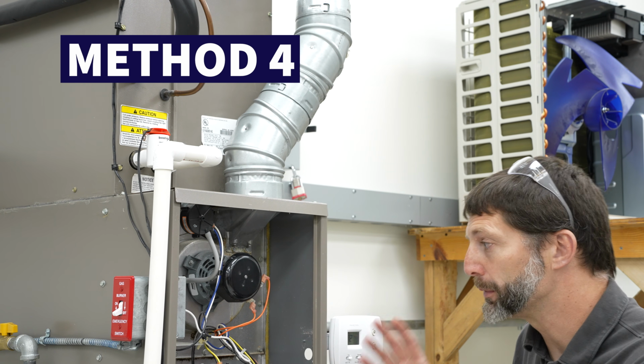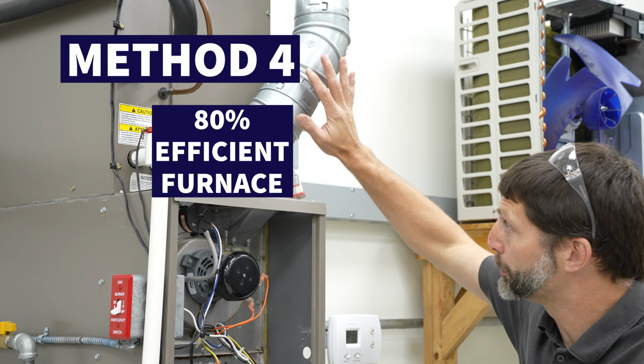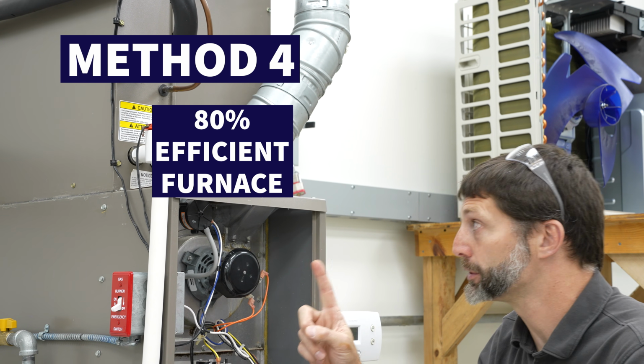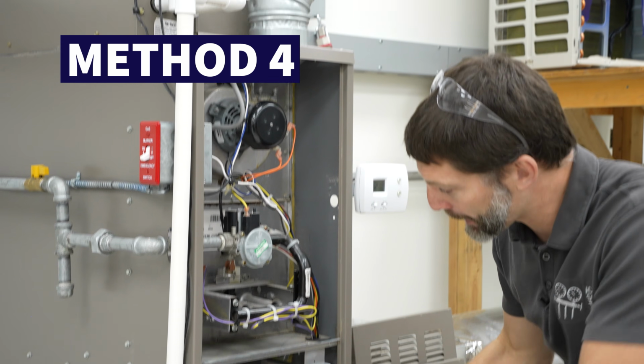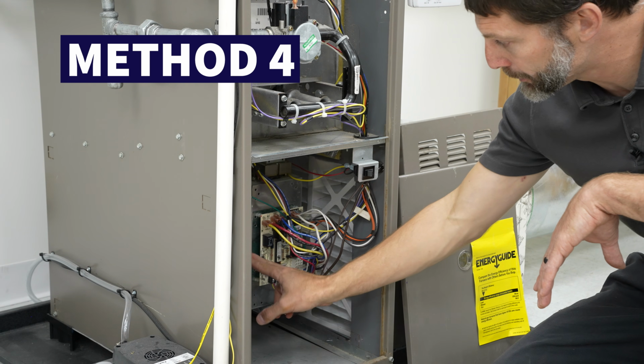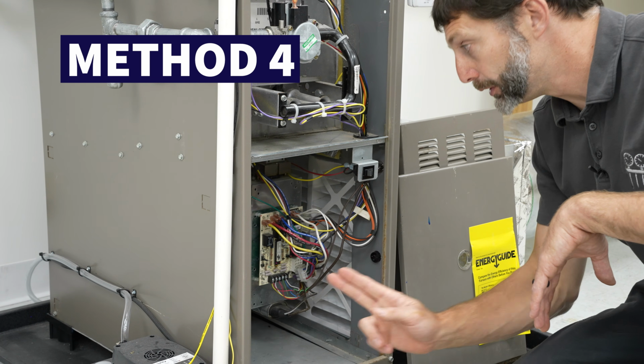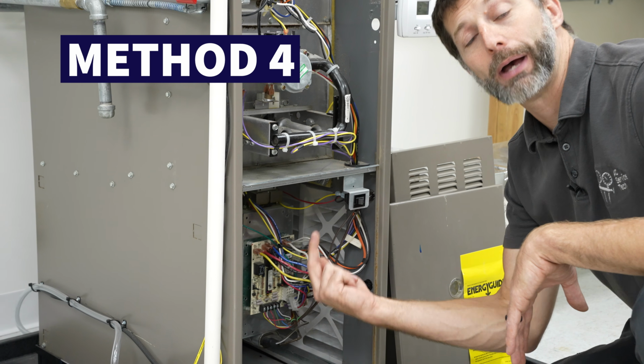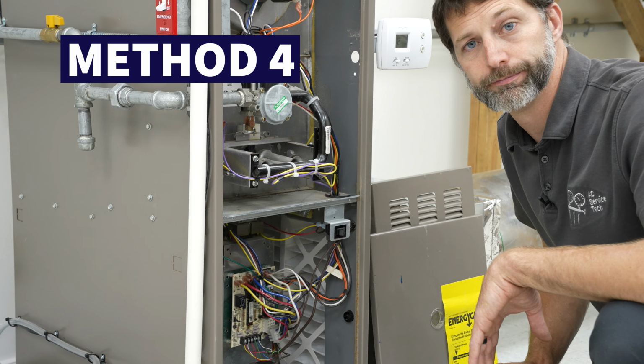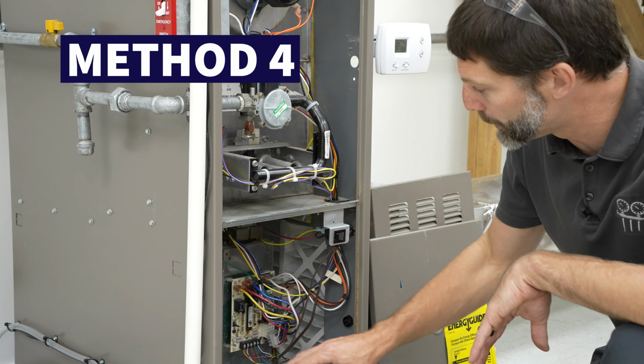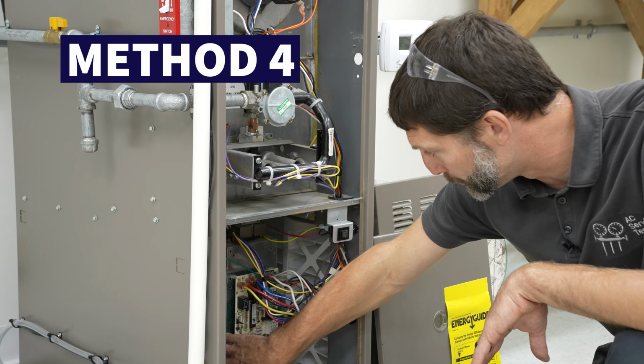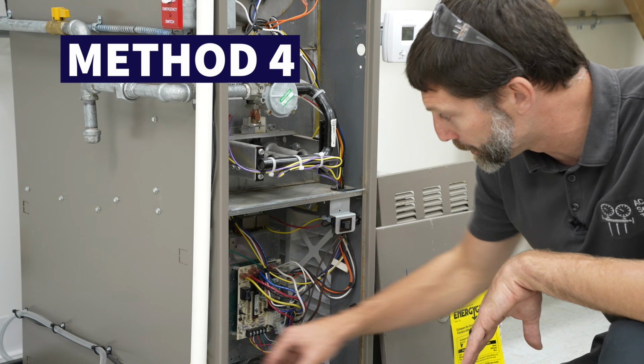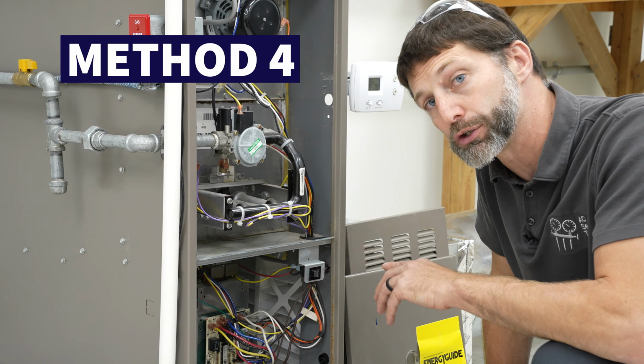Method number 4 can be used on 80% efficient furnaces because they only have one single heat exchanger, and so down here we can remove the electrical compartment and also the blower motor and look in and up past the heat exchanger to the coil. So the first thing that I'm going to do is I'm going to make sure the power's off, and I'm going to remove the electrical and also the blower motor. Make sure to take a picture before you start.